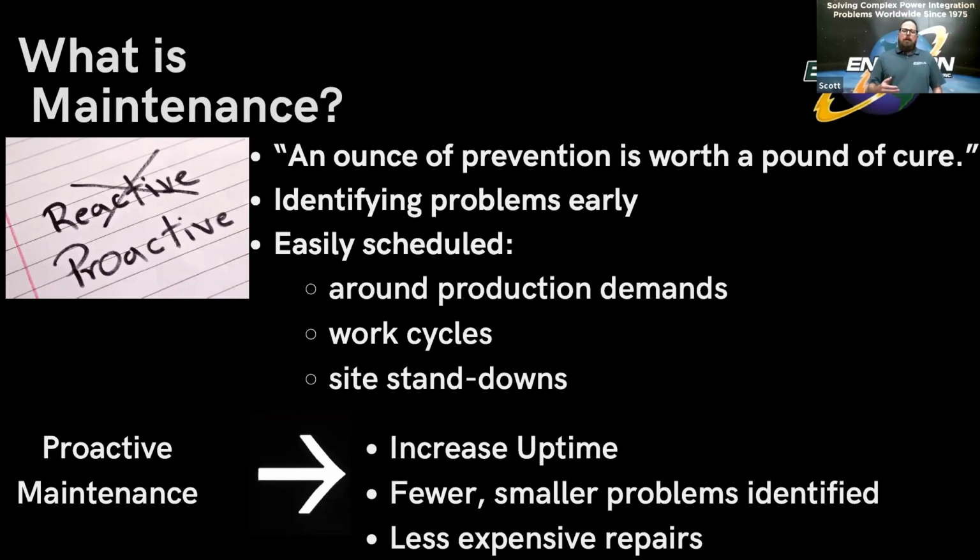Oh, sure. A proactive maintenance posture would have identified they had a component failure inside their gear that, if it had been caught during a monthly test, would have resulted in recognizing that the equipment was going to be in reduced status for the period of time it took to get that one component replaced. Instead, they ended up reverse powering their generator and then ultimately damaging their actual generator as well as the gear itself. So that one small problem grew into a much larger problem because they didn't identify it early, and then ended up trying to just run the generator into the ground.